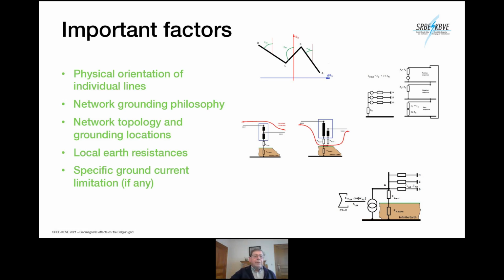Fourth important factor was already mentioned, the local earth resistance. The higher the resistance, the lower the current into that particular neutral point. But higher resistance shifts the current, which cannot flow in this point, to other points. So influencing the earth resistances, or changing them by adding additional resistors by a specific ground current limitation, is a possibility, but you have to do it carefully, because the current you take away from one point will move to another point, and maybe it's even worse there.